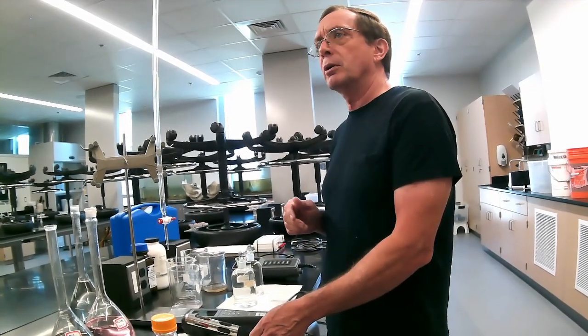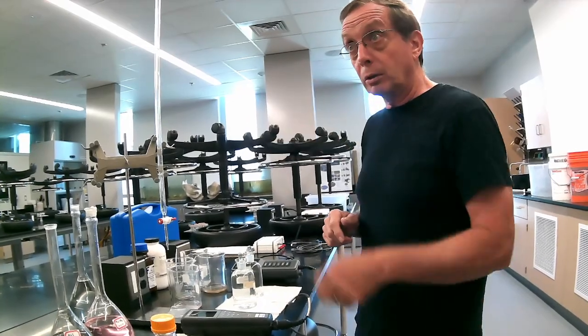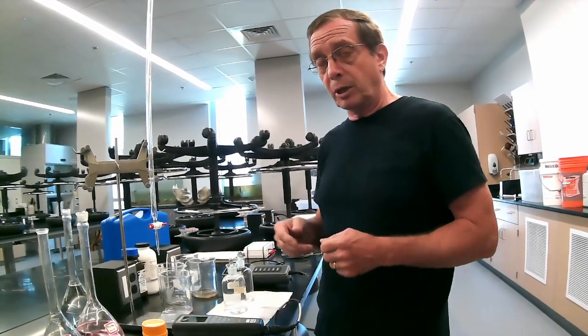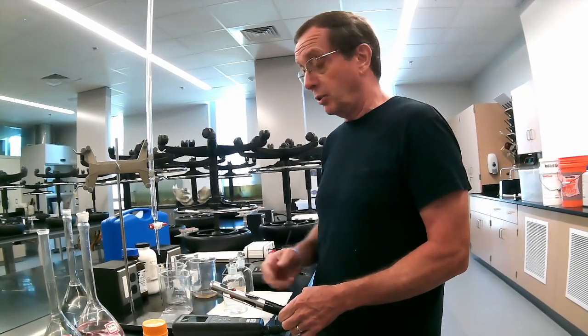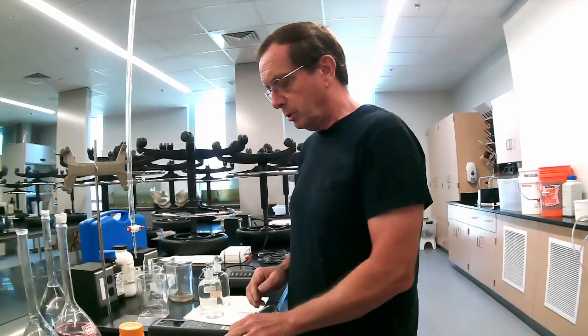The other thing, and we talked about it only briefly when we were looking at the Clark electrodes at the board: as the oxygen moves down and comes in contact with the cathode, the oxygen is consumed in the reaction. And so if you have to be really, really accurate with a Clark electrode, you have to account for the amount of oxygen that's been picked up by the electrode and doesn't come back into solution. Okay? Now the red shift types of instruments, on the other hand, don't consume the oxygen. So you get exactly the number that the meter reads. Okay, so they're relatively straightforward and easy to use.